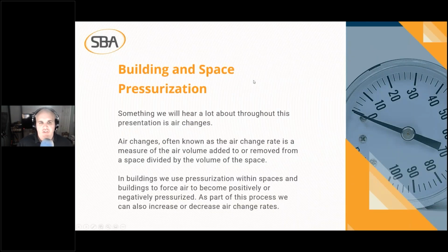Building and space pressurization. Something we hear about a lot throughout this presentation is going to be air changes. So we're going to focus in on air changes, both for COVID mitigation strategies as well as just for general pressurization strategies. For those of you who don't know, an air change is also known by the term air change rate. It is basically the measure of the air volume added to or removed from a space divided by the volume of the space. That's the air change rate. And an air change is simply replacing the entire cubic volume of air within the space.